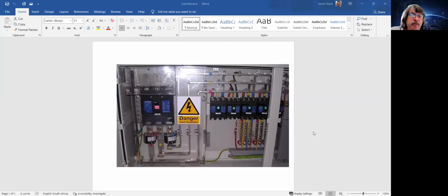I can see that these appear to be Mitsubishi products, somewhere in the region of 600 to 800 amps here, and 250 amp products as a mid feed going out this side. Some are not connected on the load side, which would probably indicate that these were there as spares, and some are connected to bus bars which have tap-offs of smaller wire, indicating possibly the use of small clip-in type products downstream.